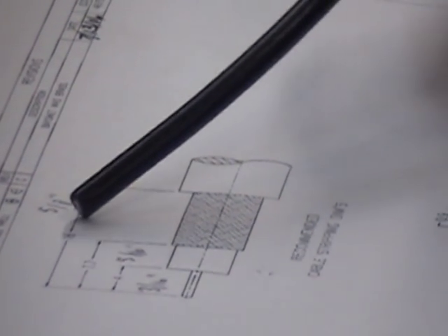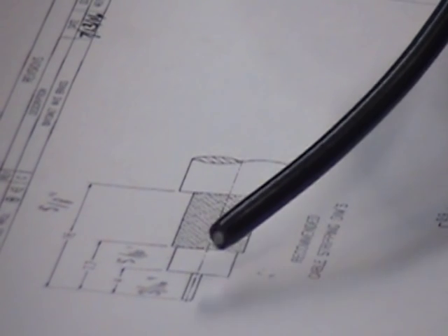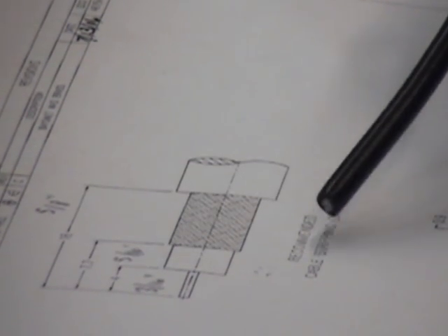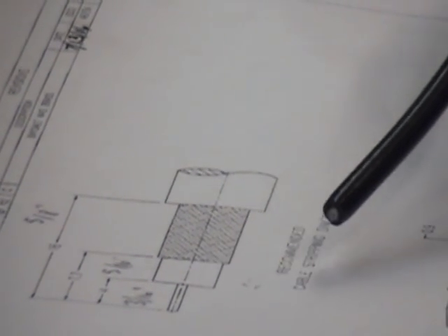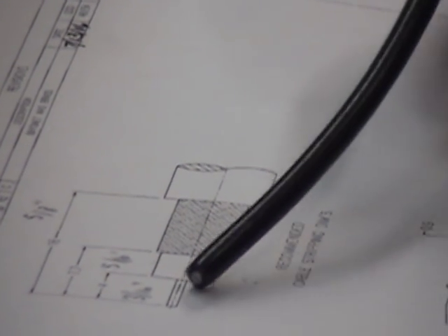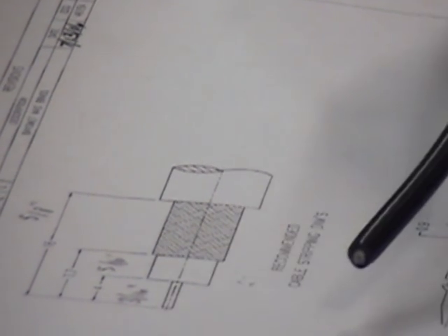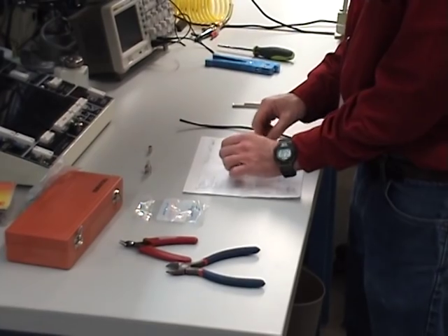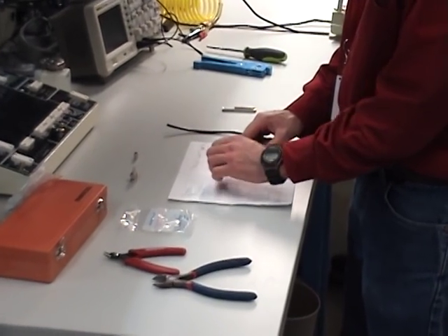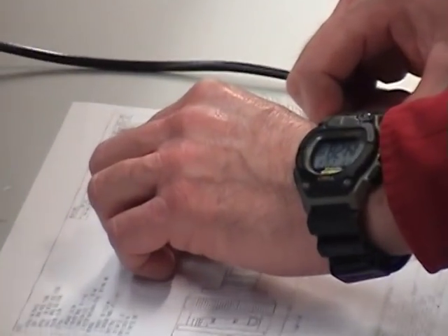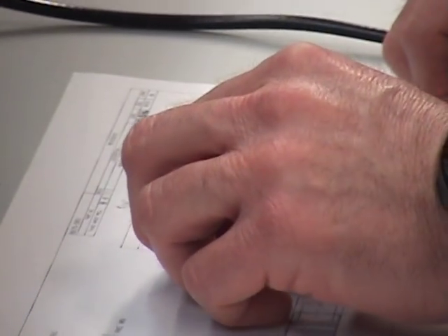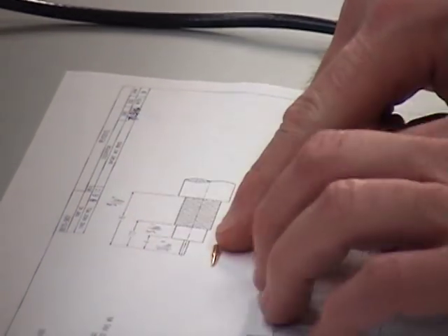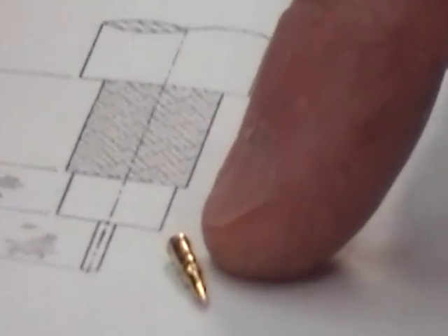In a lot of cases, they'll give you the specs in metric. Like, for instance, 4 millimeters, 7.7 millimeters, 16 millimeters. I wrote for myself, it's approximately 3/16ths of an inch, 5/16ths of an inch, 5/8ths. These stripping dimensions are important because when I look at my center conductor, I need only 3/16ths sticking out. Then I'll have my connector pin, and my connector pin must go directly over that 3/16ths. The 3/16ths will allow it to have enough depth to be inside my window, where I can see the wire stripped to the window, and then up against the dielectric.